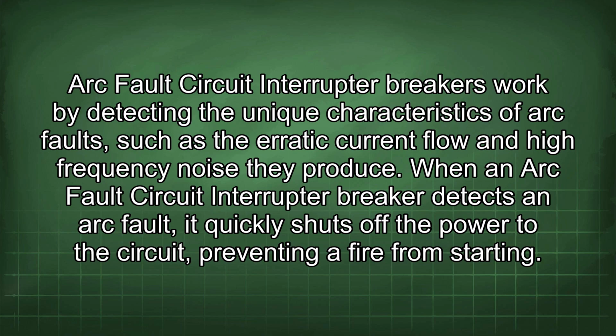Arc fault circuit interrupter breakers work by detecting the unique characteristics of arc faults, such as the erratic current flow and high-frequency noise they produce. When an arc fault circuit interrupter breaker detects an arc fault, it quickly shuts off the power to the circuit, preventing a fire from starting.